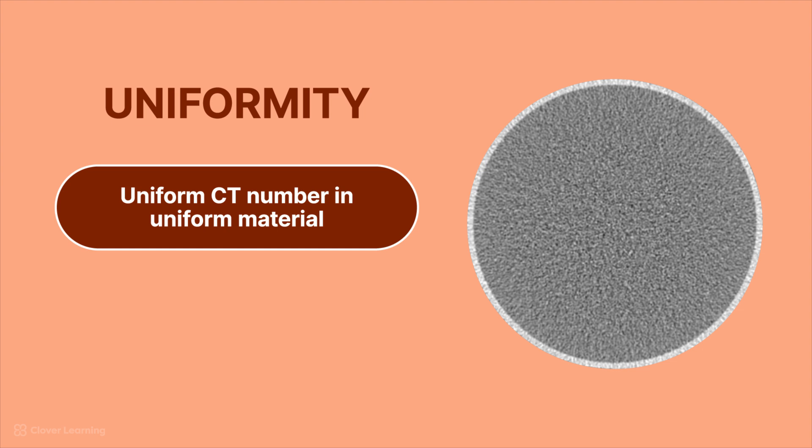In other words, all of the CT numbers should be uniform. In this uniformity phantom that we're looking at to the right, this is a water phantom. And if we place an ROI over the center of the water phantom, we might get something like three Hounsfield units. If the scanner has good uniformity, that means that if we place the ROI on the edge of the phantom, we should still get something very, very close to the same Hounsfield units.